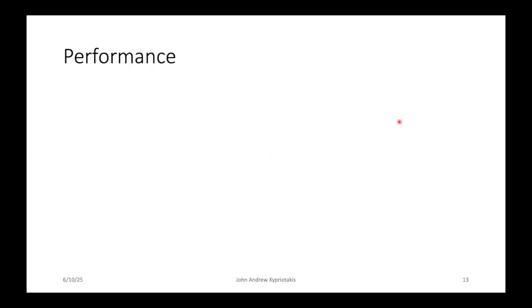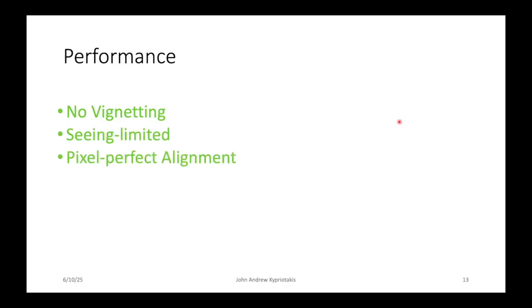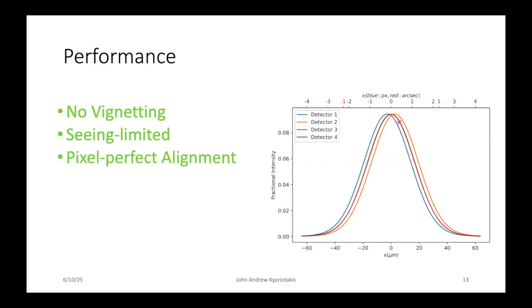Now let's discuss the performance of an instrument because, well, I've shown you one design that works, but does it work? Well, it introduces no significant vignetting above the vignetting of the telescope itself. It is indeed seeing limited. It has pixel perfect alignment, and both those two effects can be shown here, since these are the PSFs expected by WALOP-North, convolved with the PSF that we measure at Skinakas for all 4 detectors. You see the 4 curves aligned within 1 pixel of our CCD.